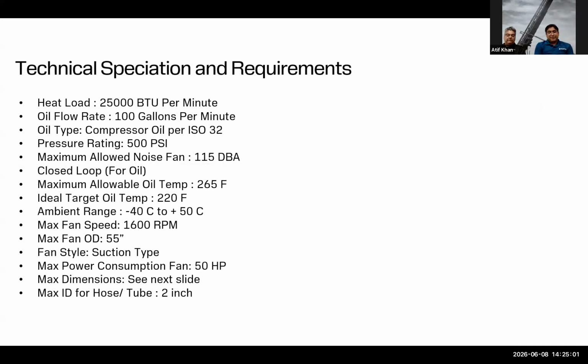Some of the technical specifications for this system are listed here. For example, the first question a heat transfer student is going to ask is what the heat load is, which is shown here as 25,000 BTU per minute. That's the heat load for the hot oil. The flow rate, as I was saying, is 100 gallons per minute. You may be interested in the oil properties like density and viscosity. There are different ISO standards for that. If you look up ISO 32, you'll find all the details. The maximum pressure in the system is expected to be 500 psi.